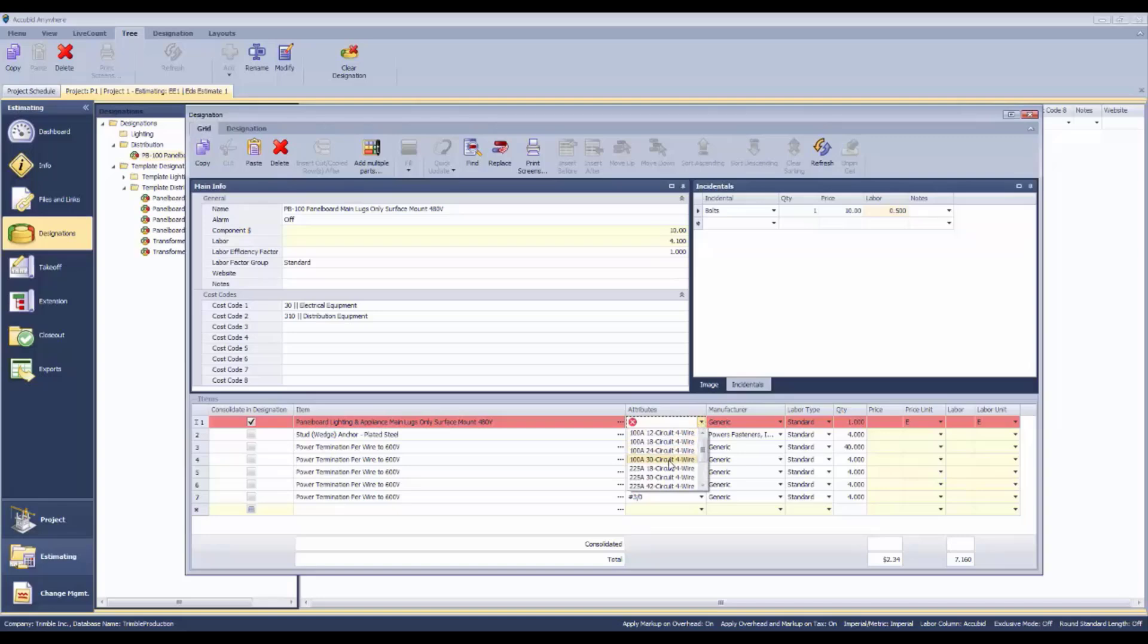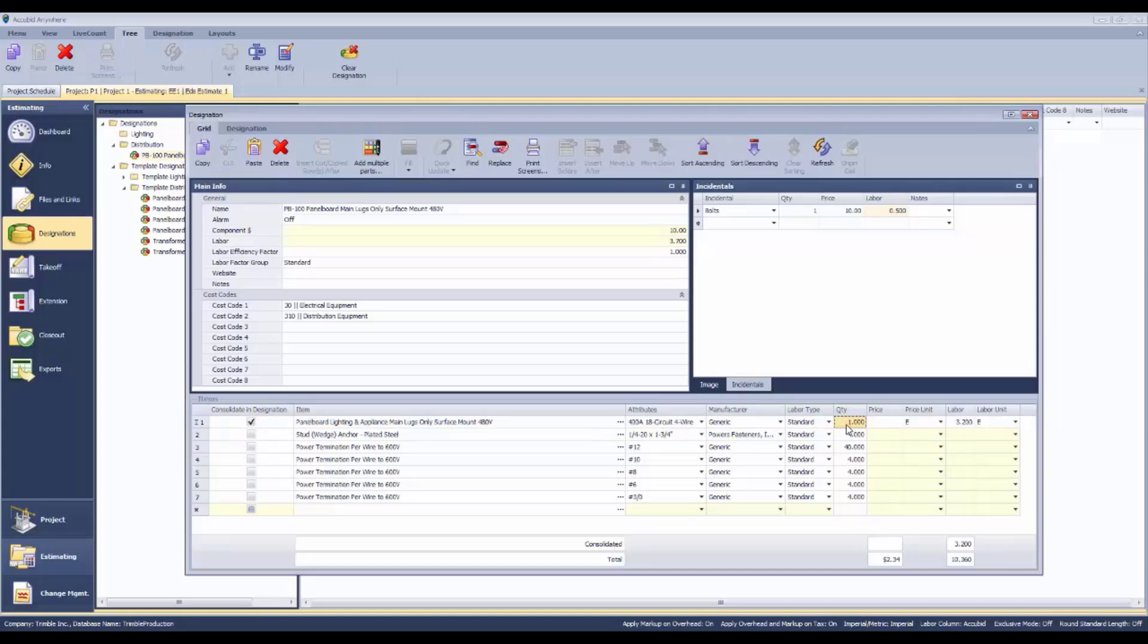We can select the specific type of panel board that we need. It's a, let's say, 400 amp 18 circuit. Then we could say that that's the particular piece of equipment. It has labor 3.2 hours and this one happens to be surface mount.